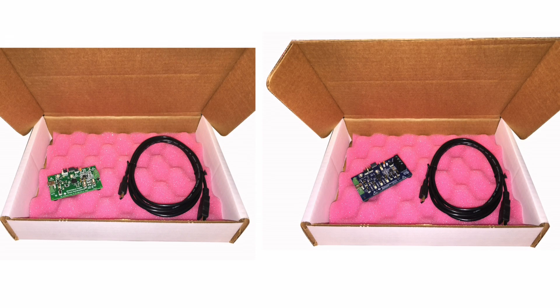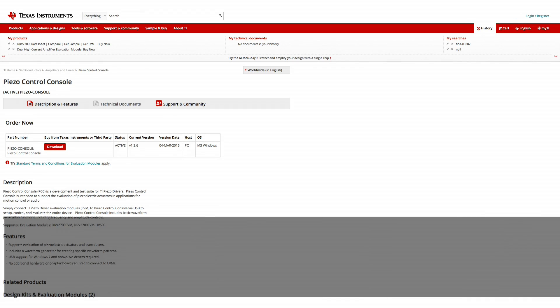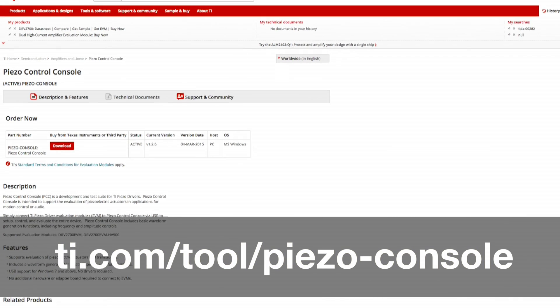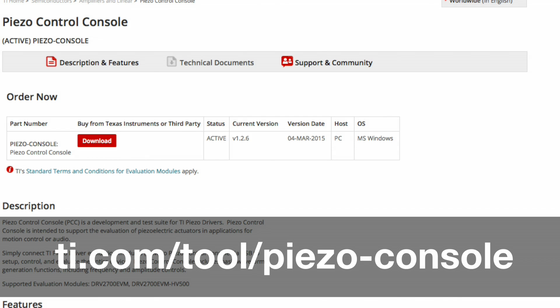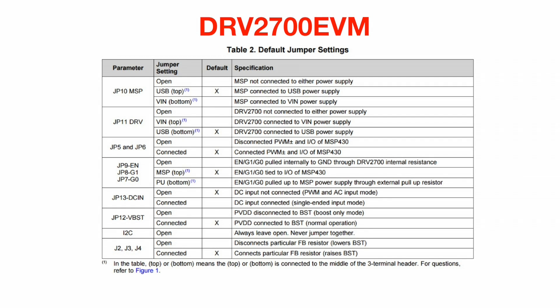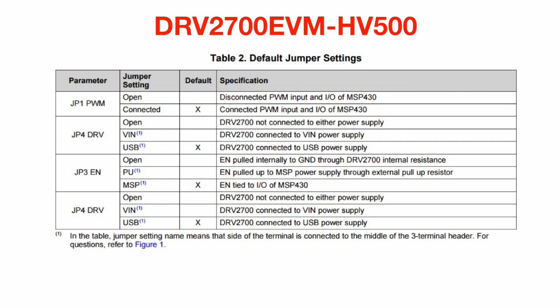Out of the box, each of these EVMs come with a mini Type B USB cable. Additionally, a graphical user interface, or GUI, can be downloaded from TI.com. After installing the GUI, make sure the default jumpers are set accordingly to the user's guide and then plug in the EVM. Run the GUI and use the USB HID communication settings and the software will identify the connected board.